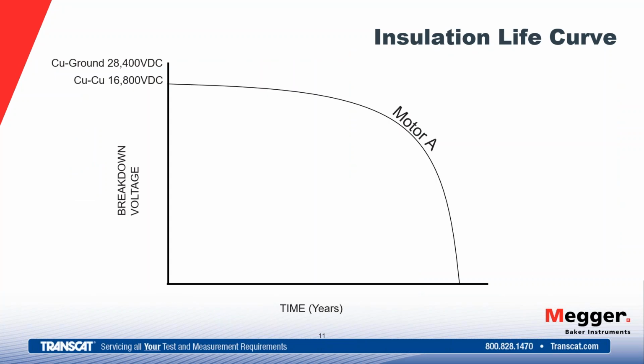So here we see what we refer to quite often as our insulation life curve. It's built around a 460 volt motor. So the y-axis there is breakdown voltage. As a motor starts its life, its breakdown voltage is very high. And it brings us to note that while the motor's nameplate voltage may be at 460, we put more insulation into that motor to give us this margin, to give us some life to the motor. So it's going to start out dielectrically much stronger than what it's rated for running. As that motor starts out, very high dielectric strength, high breakdown voltage, but then we put it to use.